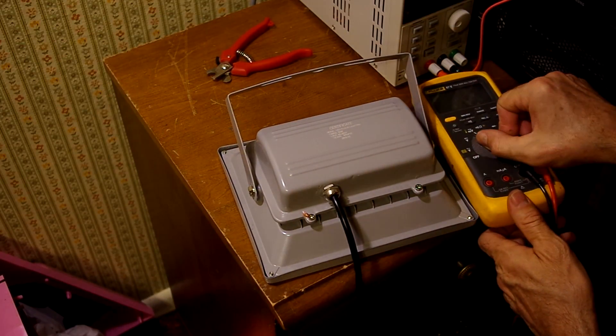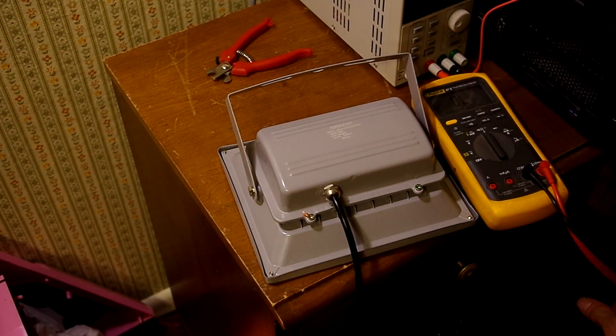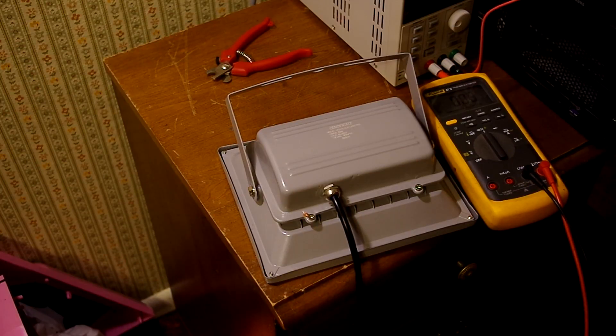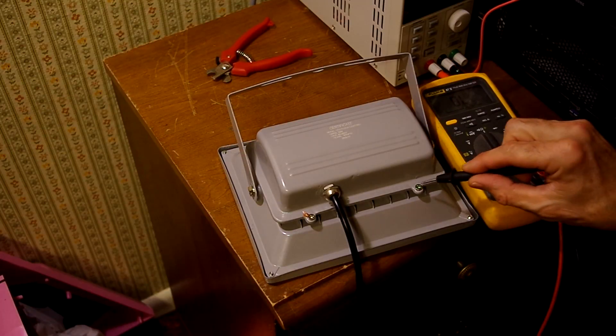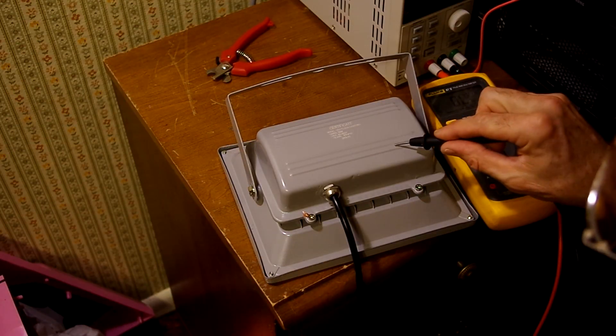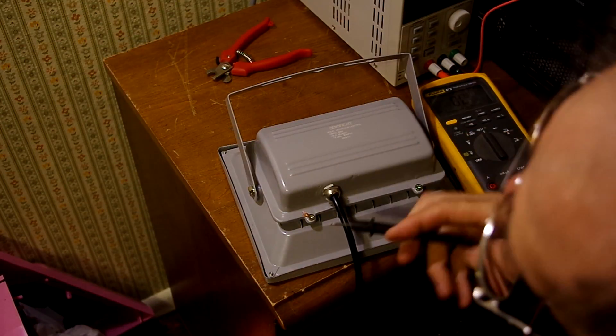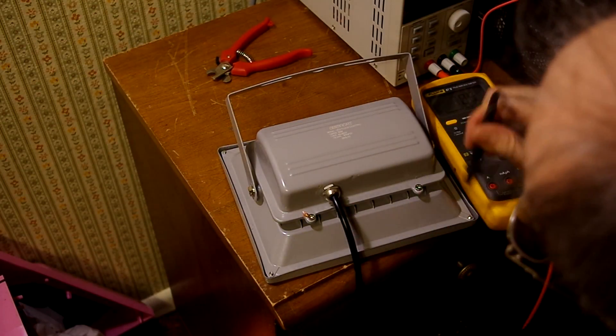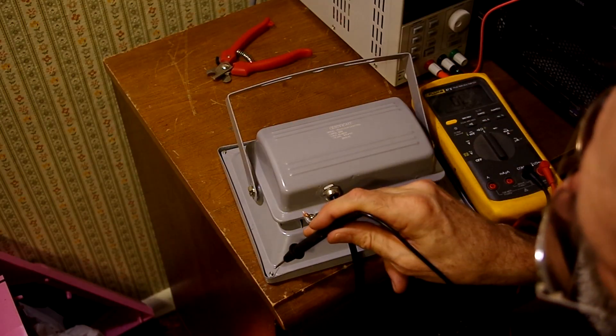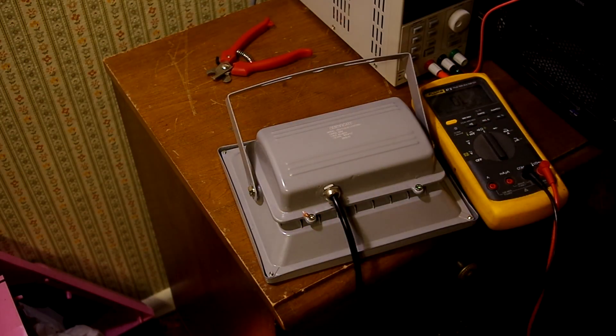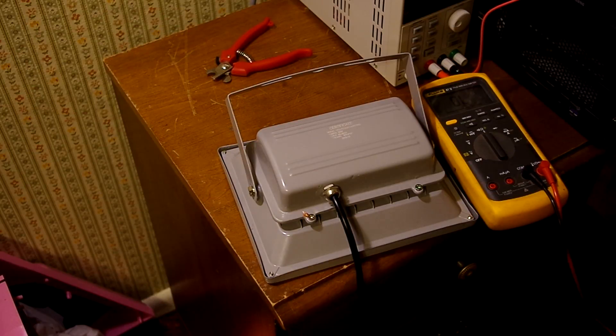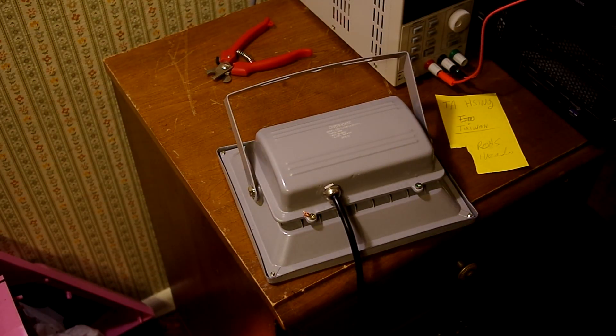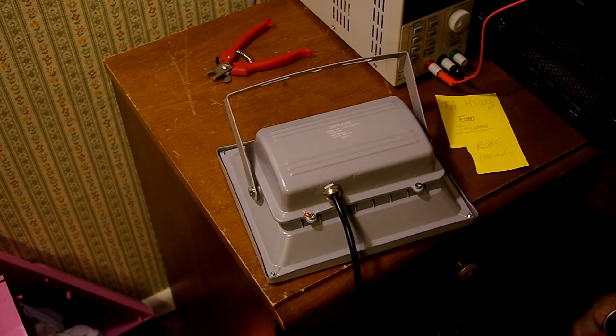Let's get the fluke meter into continuity mode. Let's check the leads, make sure it has continuity. Yeah, it works just fine. So let's check and make sure it's earthed. I got one end to the earth plug. The painted surfaces aren't going to have continuity, but the screws all work fine. So we've got the earth ground connected up just fine. So the next thing we're going to do is plug it in and see if it actually produces light.